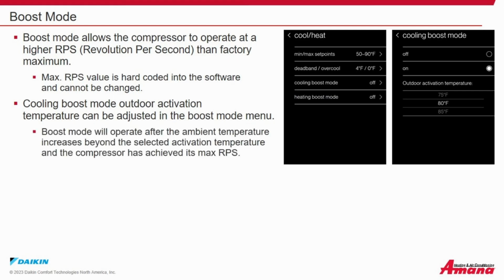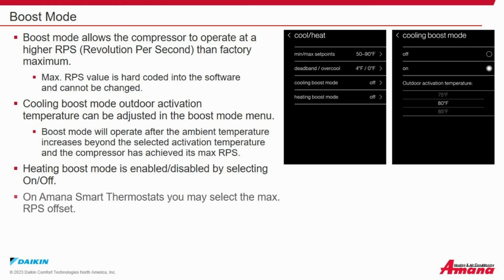Boost mode will operate after the ambient temperature increases beyond the selected activation temperature and the compressor has achieved its maximum revolutions per second. Heat boost mode is enabled and disabled by selecting On/Off. On Amana Smart thermostats, you may select the maximum RPS offset. This allows you to adjust plus 10% RPS from the factory maximum RPS.